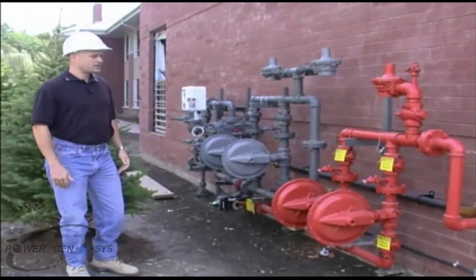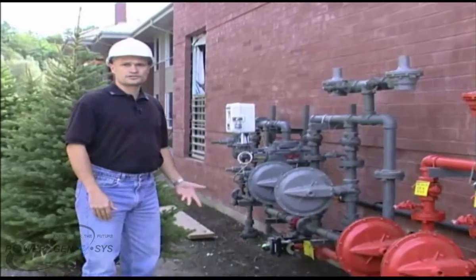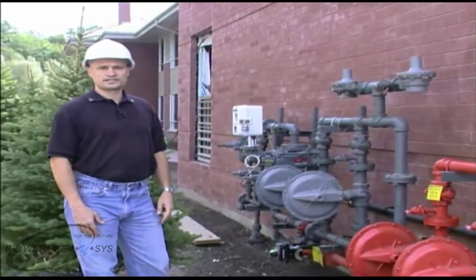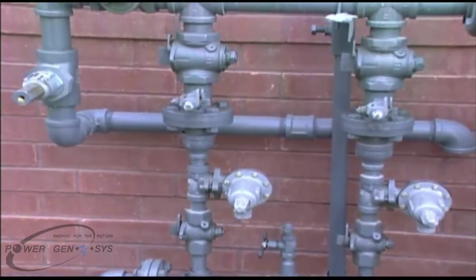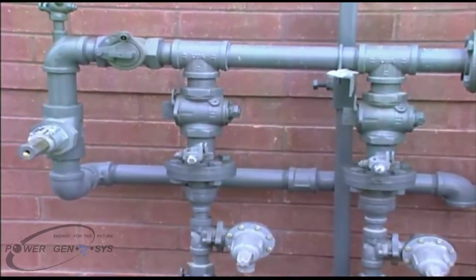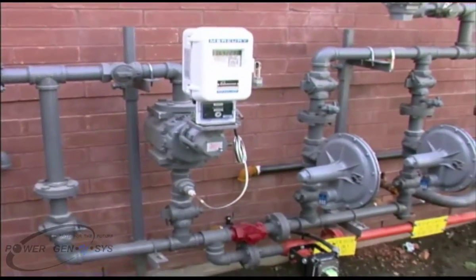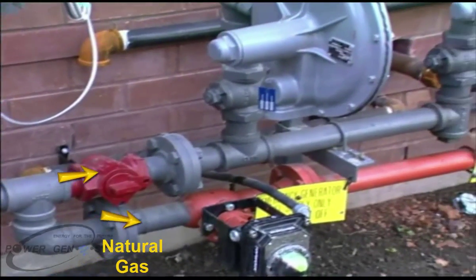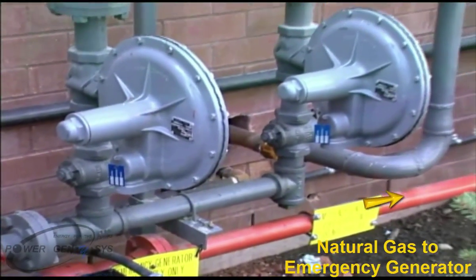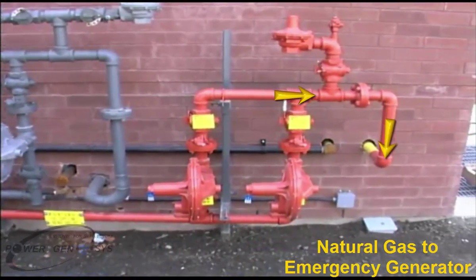What we have here is an emergency power supply system based on natural gas. Typically those installations are diesel, but the new standard — CSA 282 2005 edition — now allows for natural gas. One of the requirements is to provide a dedicated gas supply line, which is what we've done here. We've come off the main line ahead of the red fire valve, supplying a dedicated line to the emergency generator. This allows the facility to operate in prolonged outage mode with unlimited fuel supply.